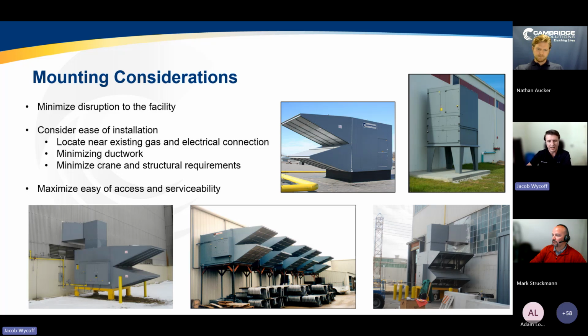You also want to think about ease of access and serviceability for the service technician. You want to make sure they're able to access the unit, preferably from the ground. As you can see, pad-mounted units are great because the service technician is able to access the control panel without getting up on a ladder. Whenever you get vertical units or units on very tall stands, you start to get into ladders and catwalks to be able to repair the unit. Sometimes this is necessary, but if you have the footprint outside, a pad-mounted unit is a great thing to consider as well.